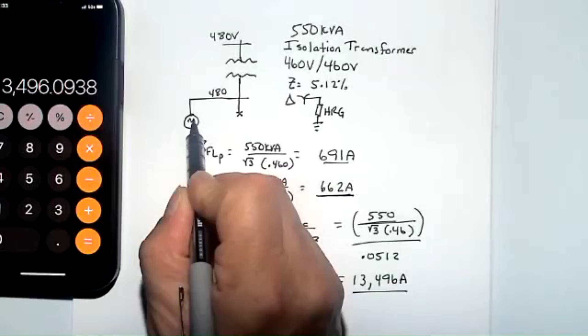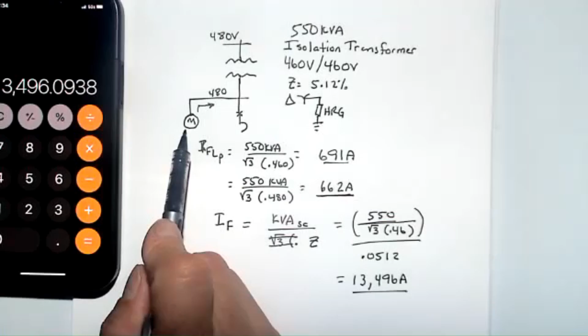If that number was 13,500 amps and you were putting 35 kA breakers in on this system, it's not going to matter. It's so different that it doesn't matter. If this number was 34,000 amps and we weren't exactly sure what the impedance up here was going to do and the motor contribution was going to do, I would be much more concerned. So again, using these estimated calculations, we can go through that and figure it out.